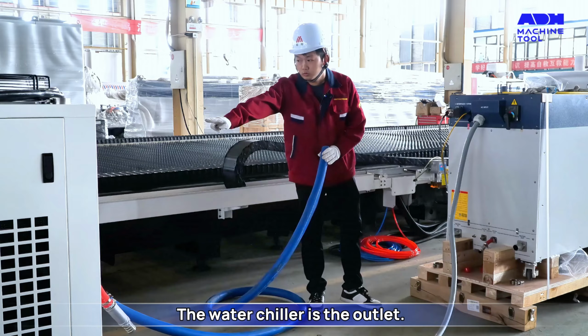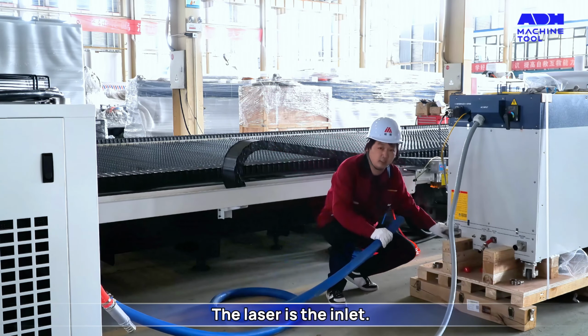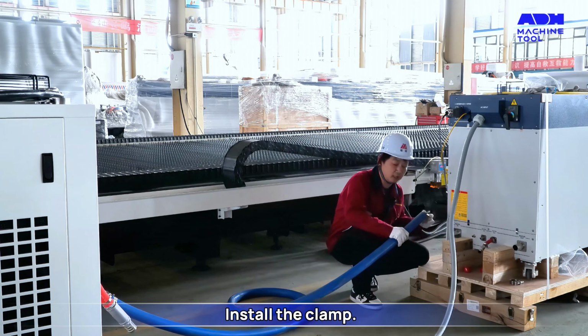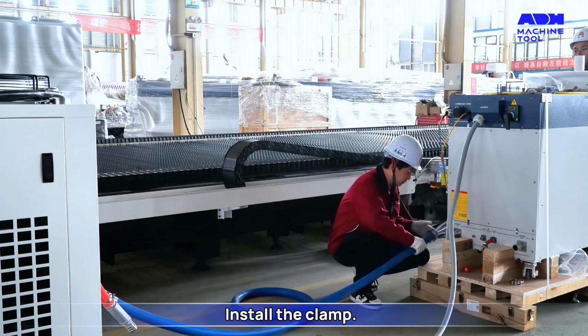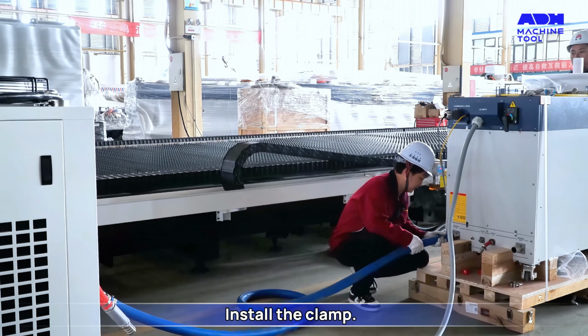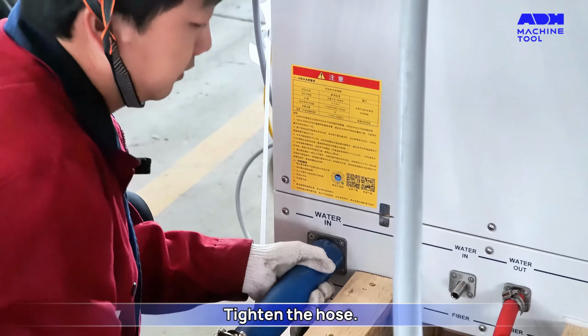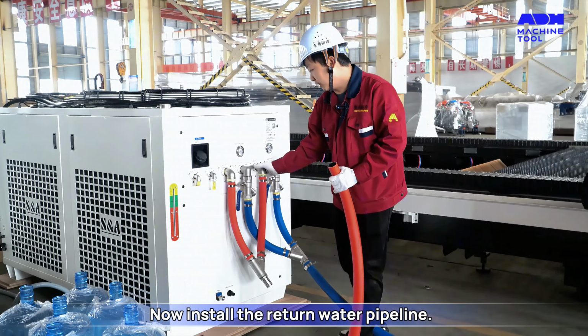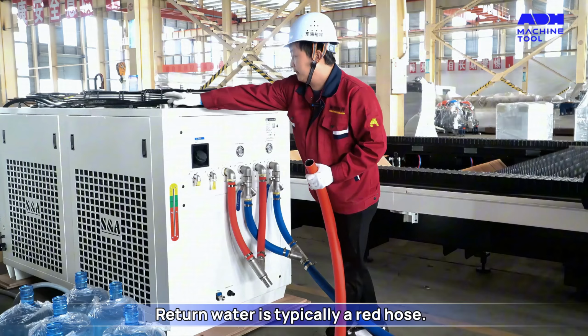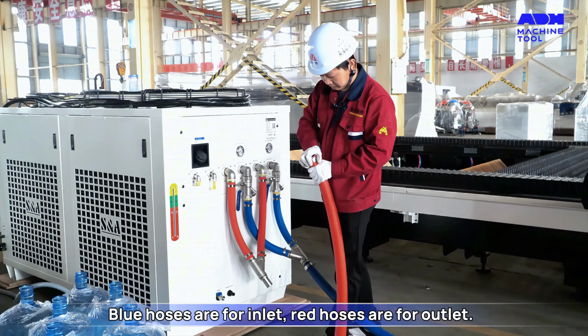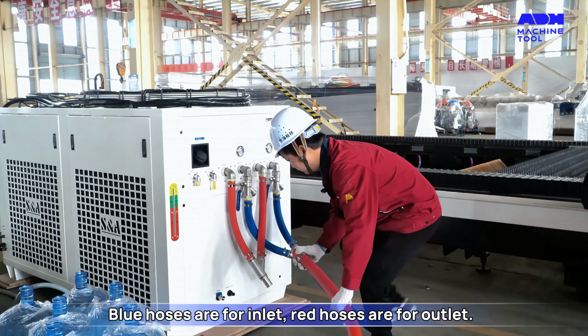The water chiller is the outlet. The laser is the inlet. Install the clamp. Tighten the hose. Now install the return water pipeline. Return water is typically a red hose. Install the clamp. Blue hoses are for inlet, red hoses are for outlet.